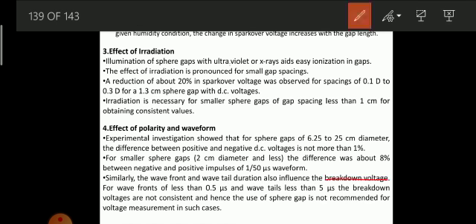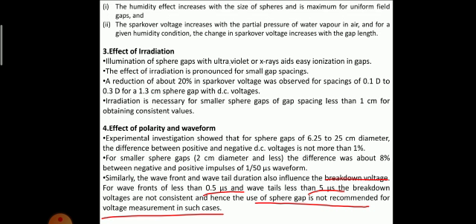For wavefronts of less than 0.5 microsecond, see, the standard impulse wave has a wavefront time of 1 microsecond. But if the wavefronts are less than 0.5 microseconds and wavetails are less than 5 microseconds, the breakdown voltages are not consistent, and hence the use of sphere gap is not recommended for voltage measurements in such cases. When your wavefronts and wavetails are not 1/50 microseconds, such measurements are not recommended.